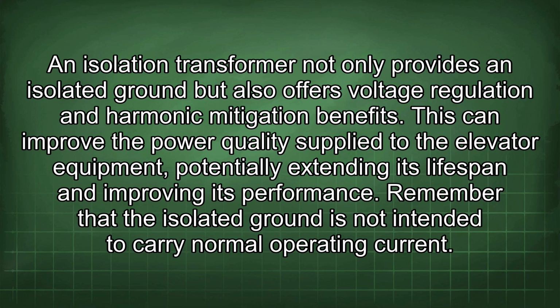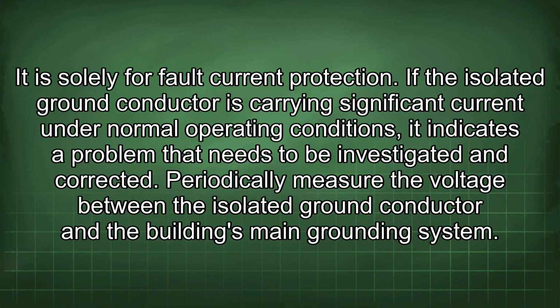Remember that the isolated ground is not intended to carry normal operating current. It is solely for fault current protection. If the isolated ground conductor is carrying significant current under normal operating conditions, it indicates a problem that needs to be investigated and corrected.